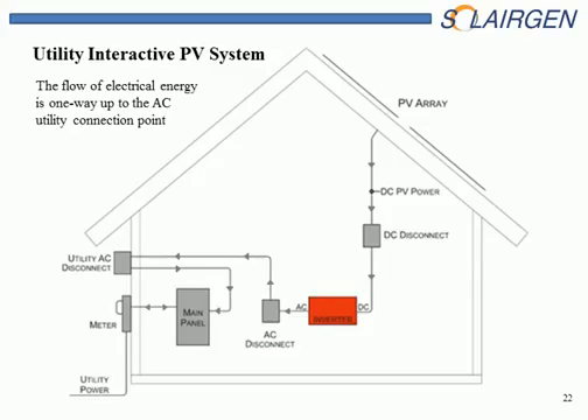So with this system, this DC disconnect would probably be located either inside the house or on the outside of the house. Either one is readily accessible. The AC disconnect may be right next to the inverter, and it may be outside or inside. If it's outside, it's probably the only AC disconnect that they're going to have, because it'll be one and the same with that utility AC disconnect that you see on the left. If it's inside the house, then there will be an additional AC disconnect, as the utility requires this in order to connect to the utility system. The power then feeds back into the main panel and then feeds into the house and of course out to the meter if it's selling power outward.